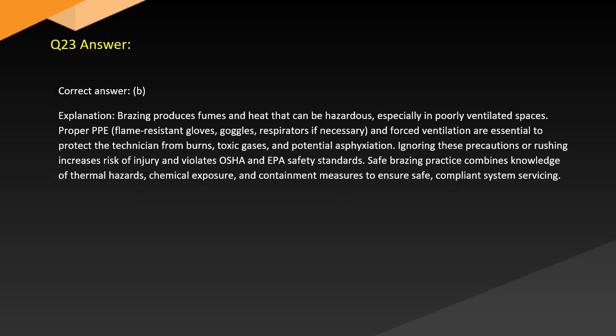Answer. Correct answer. B. Explanation. Brazing produces fumes and heat that can be hazardous, especially in poorly ventilated spaces. Proper PPE, flame-resistant gloves, goggles, respirators if necessary, and forced ventilation are essential to protect the technician from burns, toxic gases, and potential asphyxiation. Ignoring these precautions or rushing increases risk of injury and violates OSHA and EPA safety standards. Safe brazing practice requires knowledge of thermal hazards, chemical exposure, and containment measures to ensure safe, compliant system servicing.